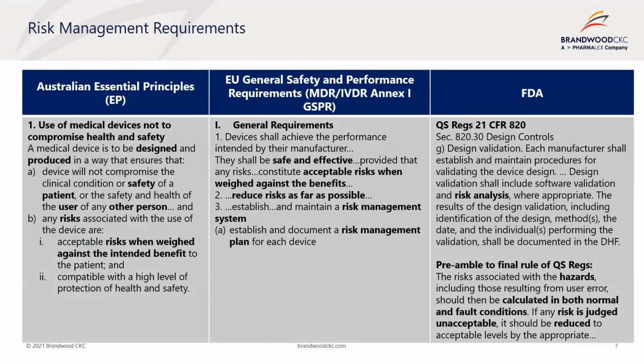Let's now look at the risk management requirements. I have provided a sample of the key regulatory requirements related to risk management that can be found in Australia, EU, and US. Shown are excerpts from the various regulations. Both the Australian and EU regulations include specific risk requirements. In Australia, it is found in the essential principles, including the Therapeutic Goods Medical Device Regulations 2002. In the EU, it is found in the General Safety and Performance Requirements, included in Annex 1 in both the MDR and IVDR.